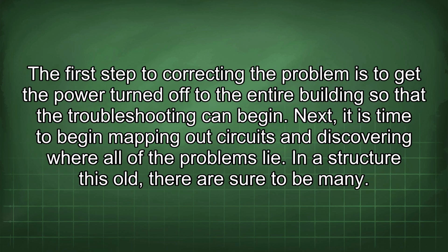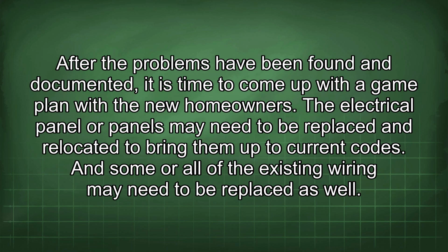The first step to correcting the problem is to get the power turned off to the entire building so that the troubleshooting can begin. Next, it is time to begin mapping out circuits and discovering where all of the problems lie. In a structure this old, there are sure to be many. After the problems have been found and documented, it is time to come up with a game plan with the new homeowners. The electrical panel or panels may need to be replaced and relocated to bring them up to current codes. And some or all of the existing wiring may need to be replaced as well.